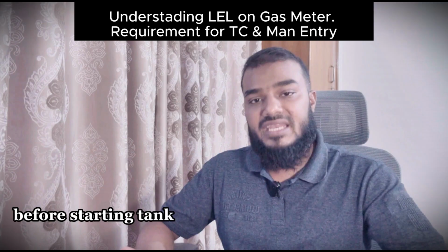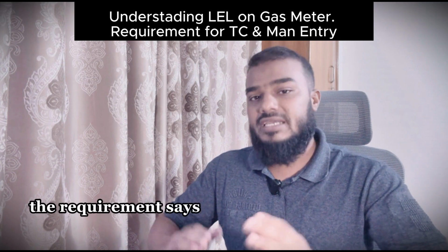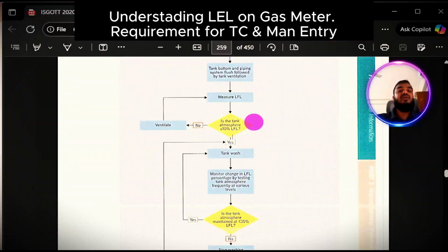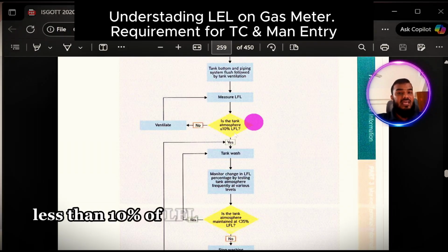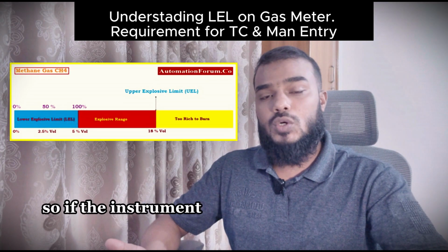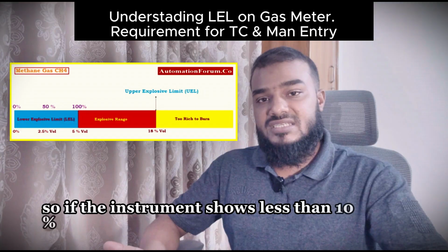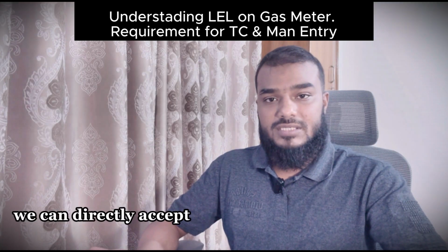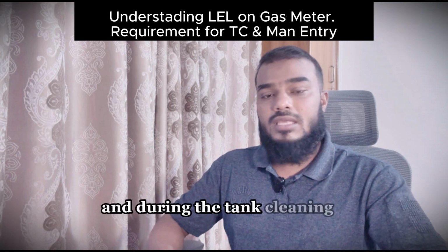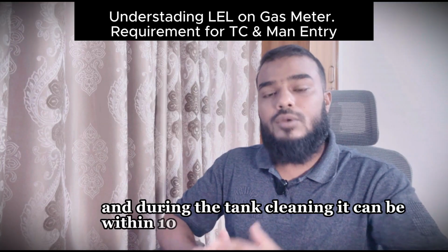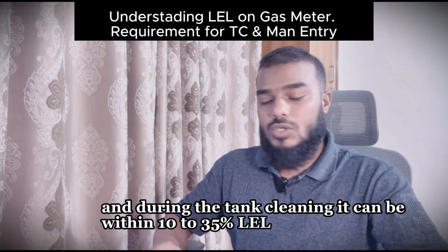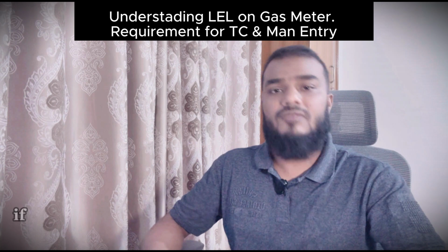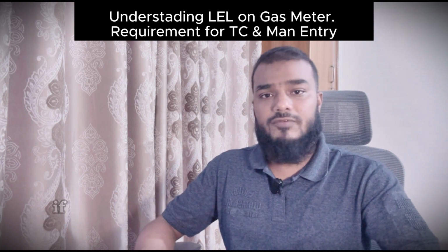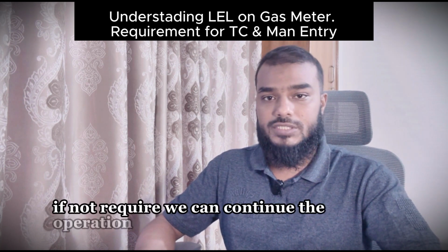Before starting tank cleaning, the requirement says it has to be below 10%, less than 10% of LFL. So if the instrument shows less than 10% LEL, we can directly accept it. And during the tank cleaning, it can be within 10 to 25% LEL. So from time to time we have to check. If required, we need the ventilation. If not required, we can continue the operation.